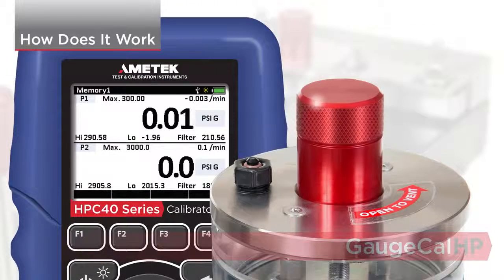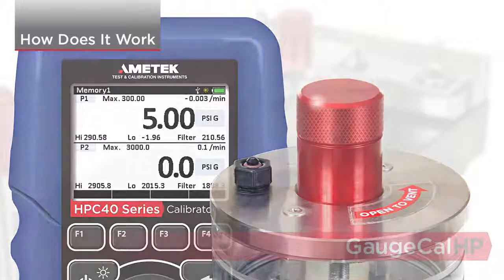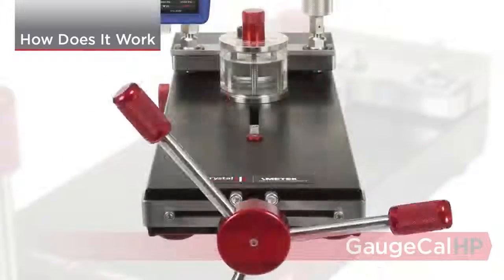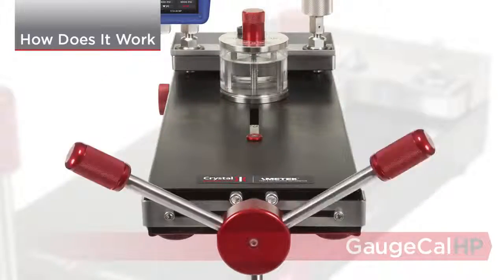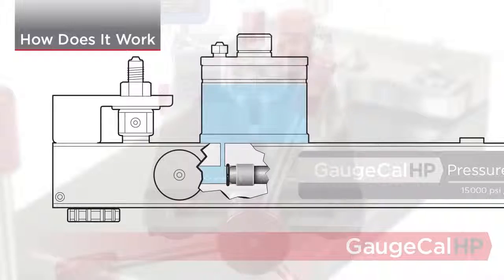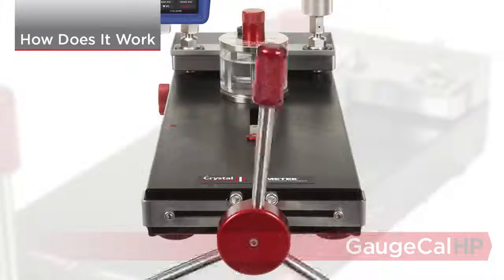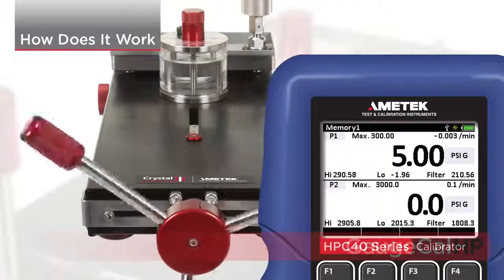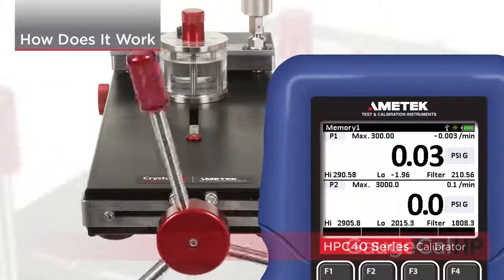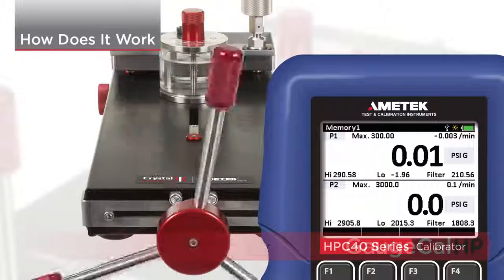Start by turning the reservoir knob to increase pressure, which saves strokes available through the main handle assembly. Once you have reached 15 psi, start increasing pressure by rotating the main handle. This will cause the piston to isolate the reservoir, removing it from the main system pressure. Continue to increase pressure to your desired point. Decreasing pressure is done gradually through the main handle assembly rather than a vent valve. This gauge-safe design avoids rapid pressure decreases that could damage the gauge under test.